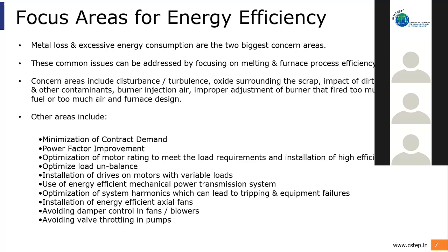Use of energy efficient axial fans. Now, fan efficiencies can be as low as 15 to 20% in many cases if the fan is not properly designed in terms of the pressure it is developing and the airflow it is delivering. And what is the type of control we have in the fan in terms of flow control? Are we having damper controls in the fan? What is the loss we are having in that damper control, whether it's a fan or a blower? That needs to be assessed.